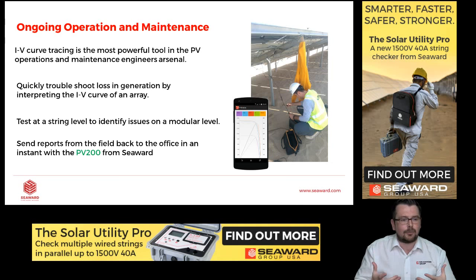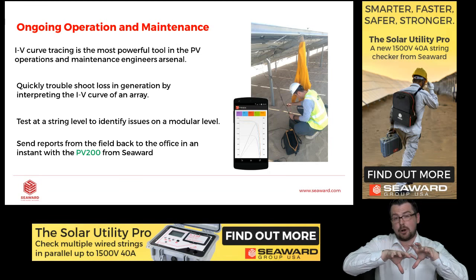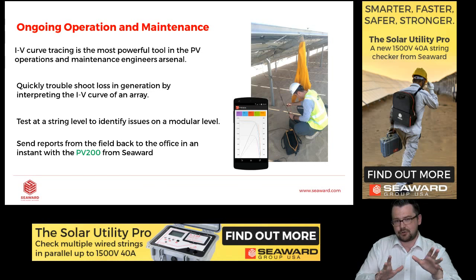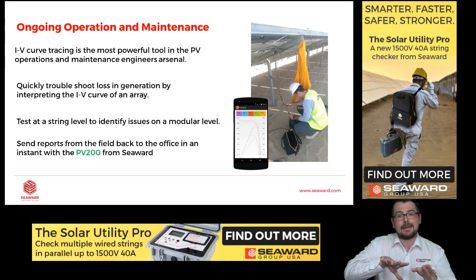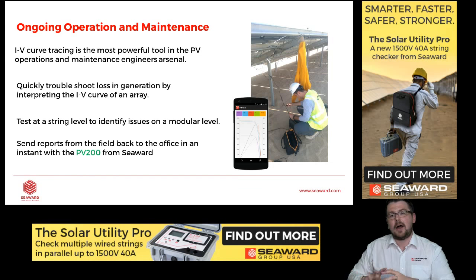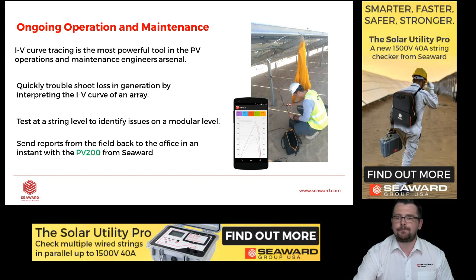So you can quickly troubleshoot generation loss. You can test at a string level to find a problem at a module level, and I'll describe how to do that for you in a second. And finally, with our instruments and the Solmetric instruments, your engineer in the field can email a report back to the office while he's on site, very, very quickly.